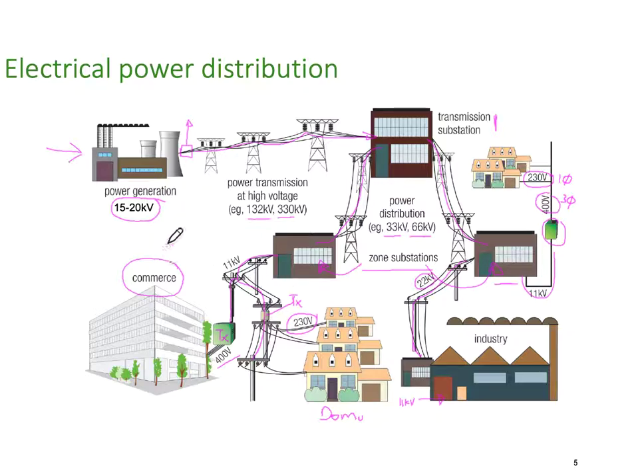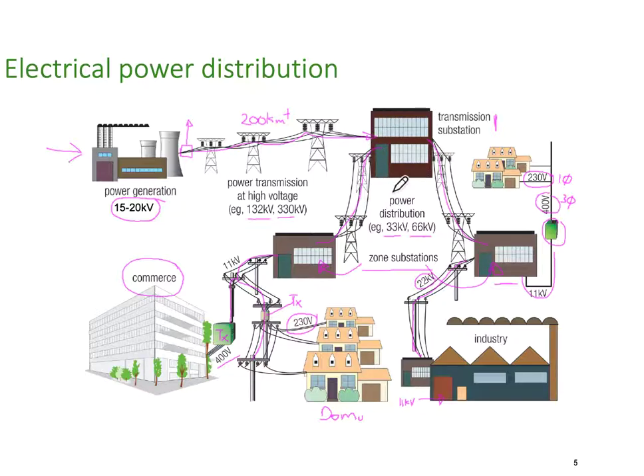To recap: generators generate at 15,000 to 20,000 volts, and we push that up into much higher voltages to transmit over long distances — typically 200 kilometres or more, even up to 2,000 kilometres. For very long distribution, very high voltages keep the current low and losses low. Then into our transmission substations, we break voltages down and distribute out to zone substations, and from there go out to industry, commerce, and domestic installations. That gives you some idea of how we reticulate electricity.